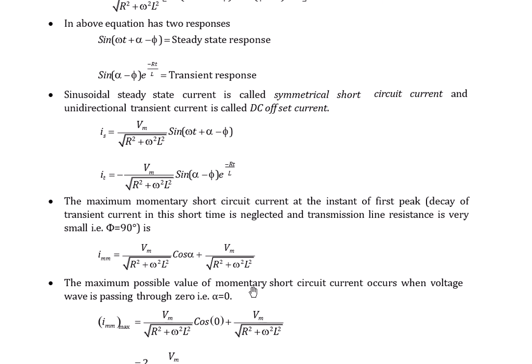Okay, so the maximum momentary short circuit current at the instant of first peak, the decay of the transient current in a short time is neglected, hence the transmission line resistance is very small. At phi equal to 90 degrees, we can put this value in this, so we can get the maximum possible value of momentary short circuit current, which occurs when the voltage wave is passing through zero. Okay, so this is how we calculate the maximum value.